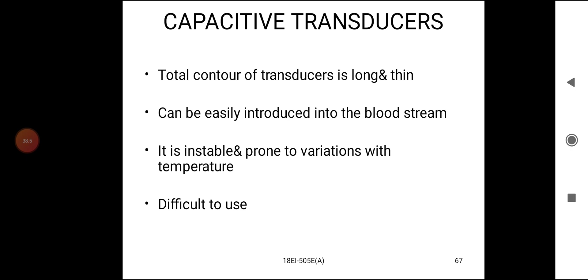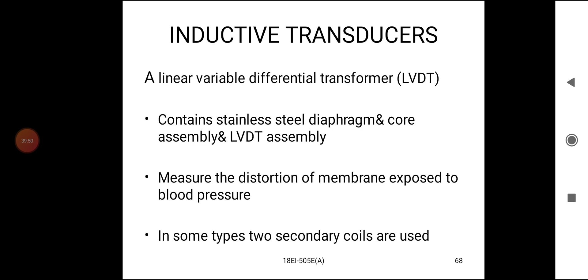Next one is inductive transducers. A linear variable differential transformer, that is LVDT, contains a stainless steel diaphragm and core assembly and LVDT assembly. It measures the distortion of the membrane exposed to blood pressure. In some types, two secondary coils are used.